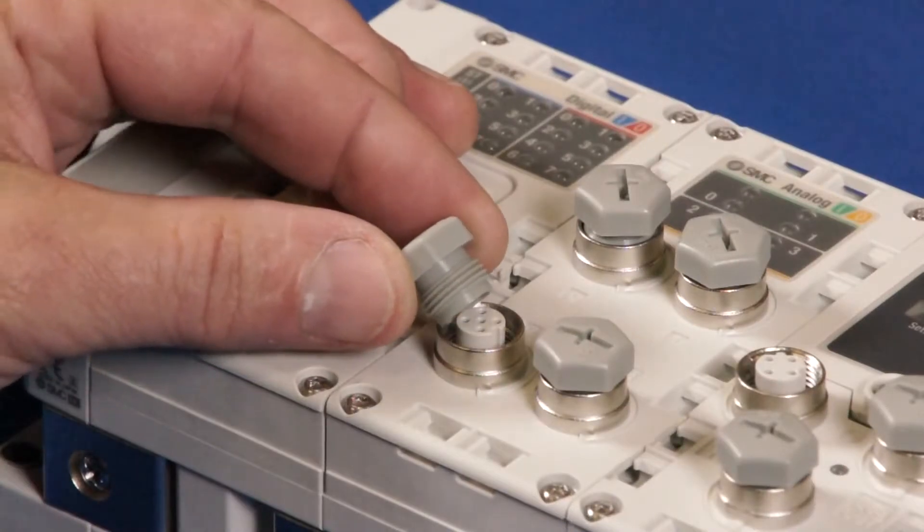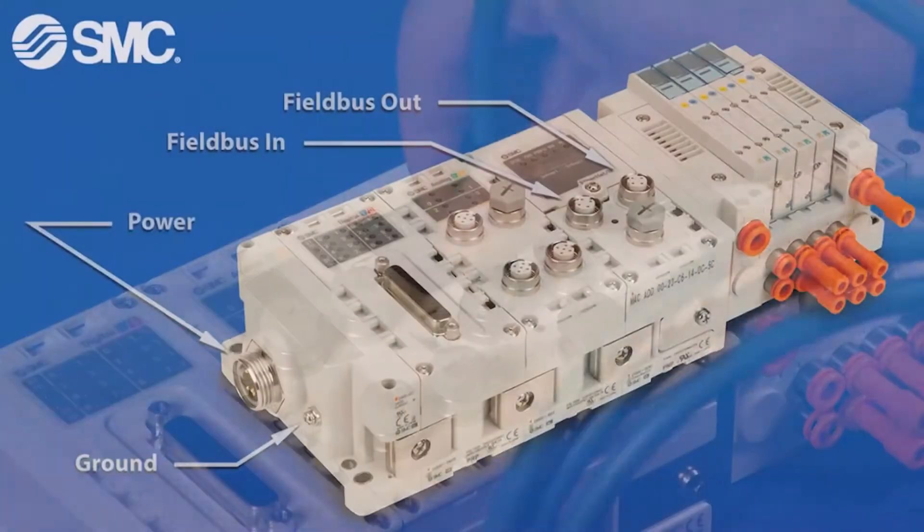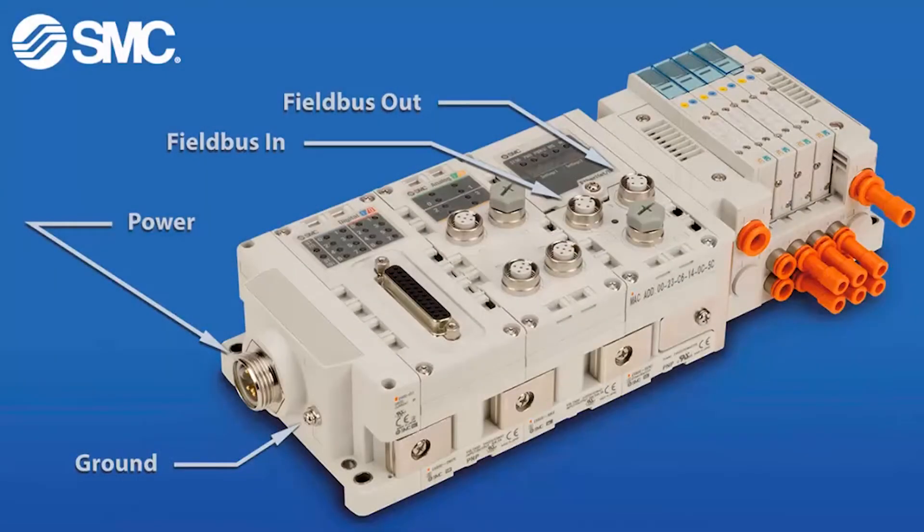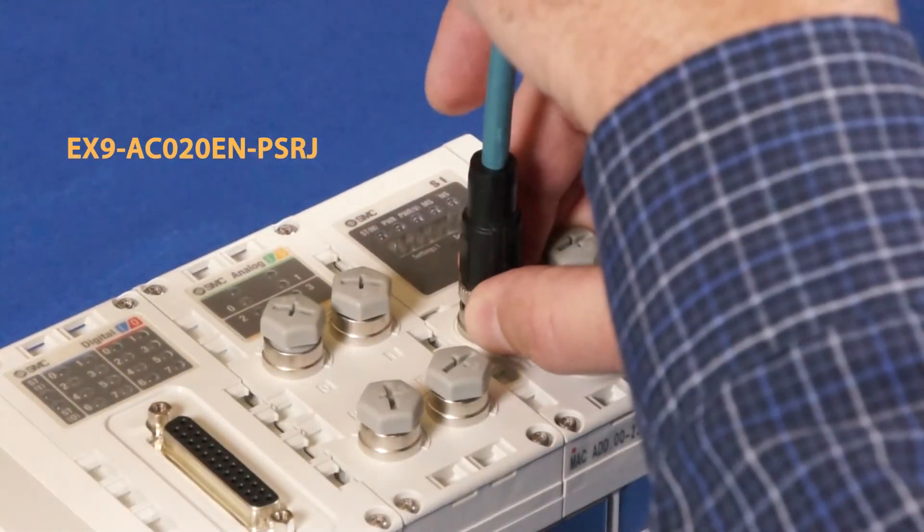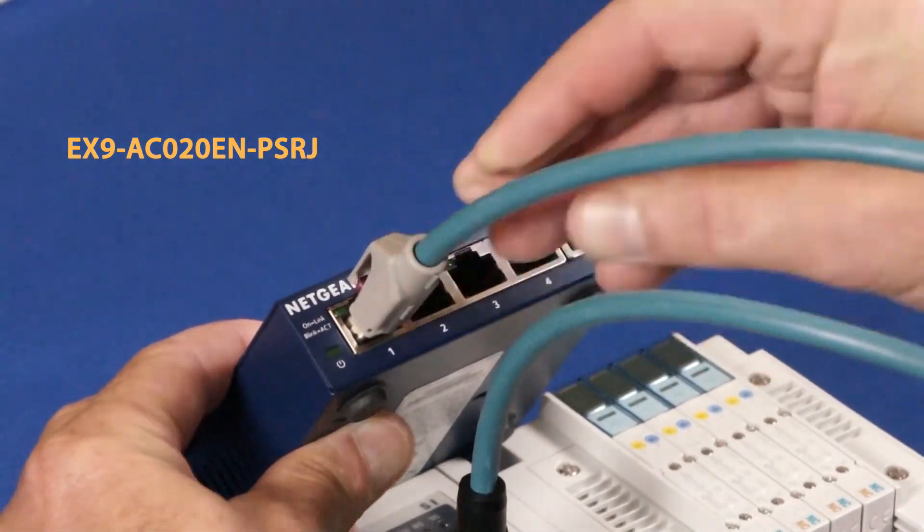Plug all the unused M12 IO ports to assure its IP rating. Now, make the field bus cable connection. Use the upper left M12 port. The RJ45 connector on the other end connects to the switch.